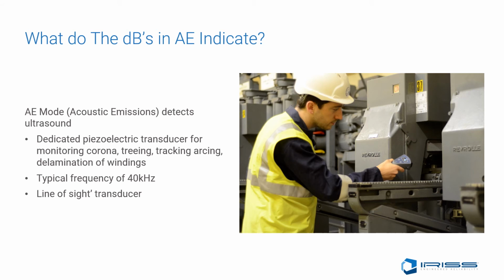So ultrasound emissions can be detected using the dedicated piezoelectric transducer for monitoring for corona, treeing, tracking, arcing, delamination of windings, and many other electrical faults that can occur inside these assets. Typically, these transducers are centered at 40 kHz, and it is a line of sight. If you cannot see the target, you will have a hard time acquiring the sound and detecting its exact source. Ultrasonic measurements rely on the fact that partial discharge will emit sound waves. The frequency for the emission is white noise in nature and therefore produces ultrasonic structure waves through the solid, liquid-filled electrical components or through air.